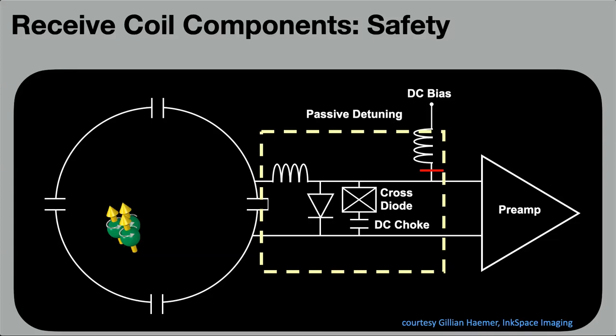Now, in some cases, a fuse must also be added to mitigate a situation where neither of these are working. It depends on your topology, but you have to think of a single fault condition where, if any component is damaged, there could be a situation with no blocking. If there is such a situation, then you have to have a fuse, which is kind of the last resort. If a lot of current goes through, it will blow up and the coil will stop functioning, but it will protect the subject. So sometimes you have to use it, sometimes you don't—it really depends on the circuitry details. Some companies, like I think Siemens, use a fuse. GE doesn't use fuses. I don't know what Philips does.